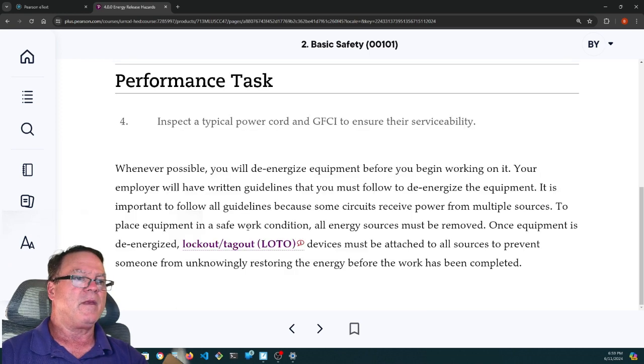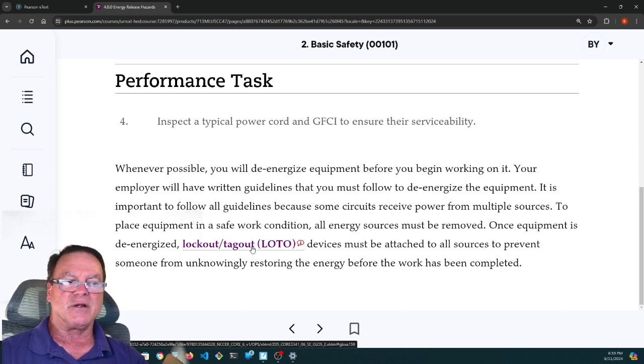So there's a whole procedure. There's a whole written manual on how you're going to do it. It's a 7-step procedure. You don't just turn it off and lock it out and you're good to go. You check it with a meter to make sure it's live. Then you check the meter on another live circuit to make sure it's still working. Then you turn off that circuit. Go check it with the meter and make sure that it's dead. Check the meter again on a known live circuit to make sure that the meter is still working. I know it sounds ridiculous, but the meter was just working a second ago, and you check it, somebody turns off a circuit breaker, you check it and it's dead. Maybe something came loose inside of that meter.